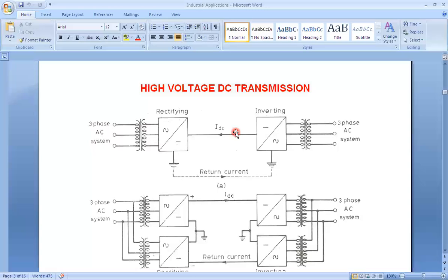First of all, in AC transmission system for three-phase power transfer, we need three or four conductors, and for that we also need tall towers. While in HVDC line, we generally use one conductor or two conductors. Therefore, due to lower mechanical load, we use a smaller size of tower in HVDC system.